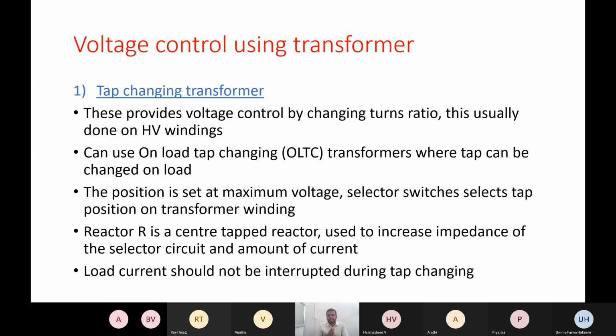Here the tap changing transformers are of two types: one is with load and another is without load. We are placing the tap changers at the HV terminal. Why are we placing them at the HV terminal? Because at the HV terminal the current will be low. As we know, current is inversely proportional to voltage, so whenever the voltage is more, the current will be less. In the high voltage terminals the current will be less, so that's the main reason why we are choosing the HV winding for placing the tappers.